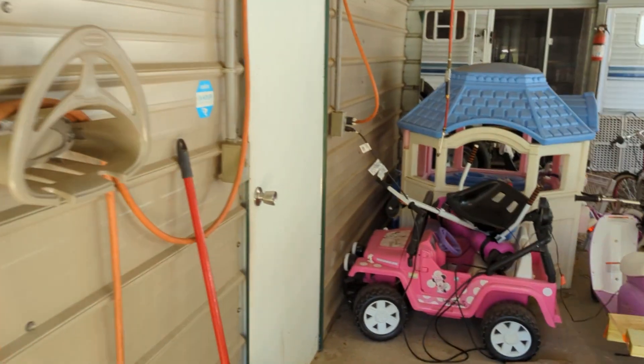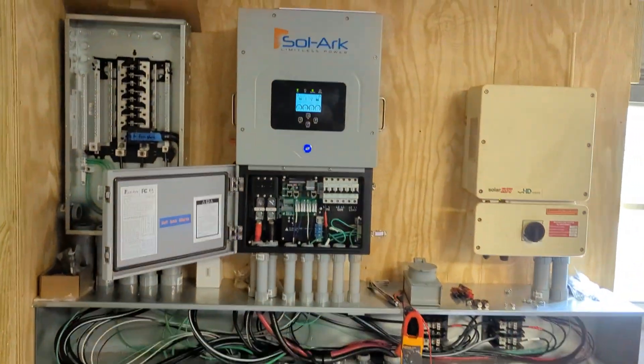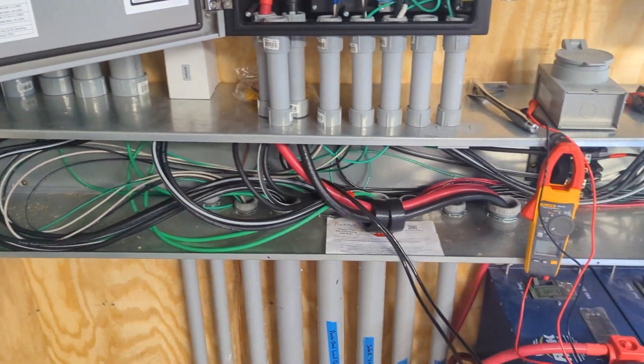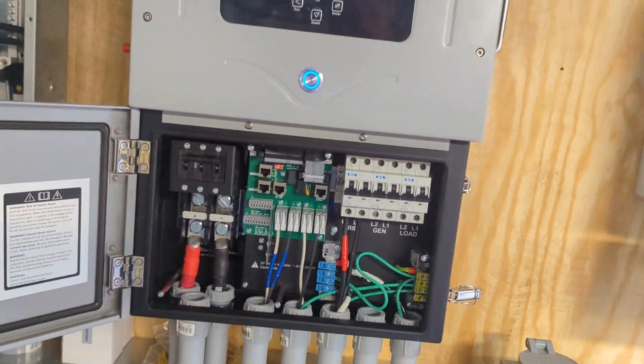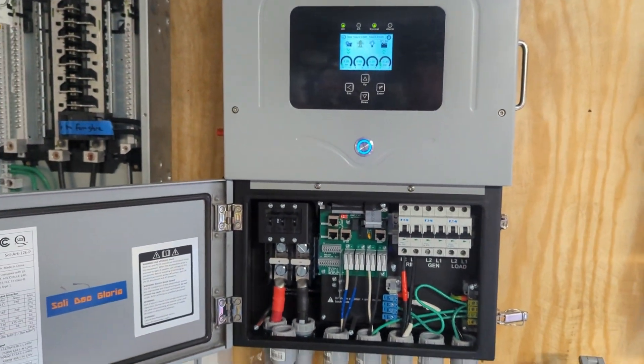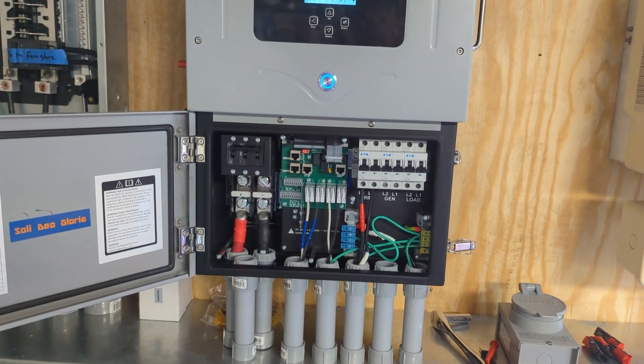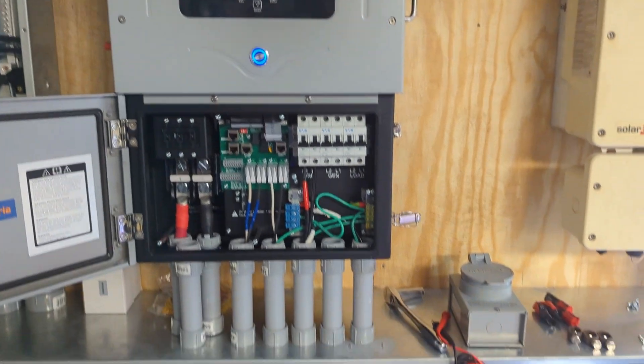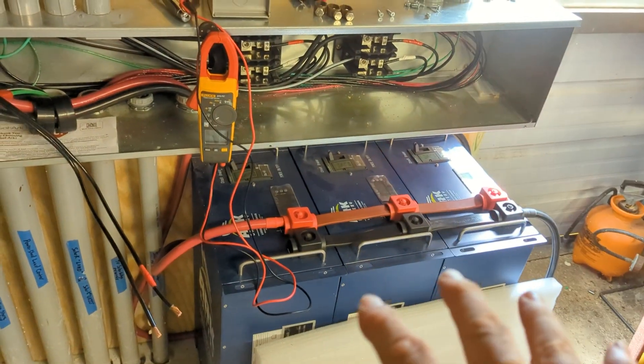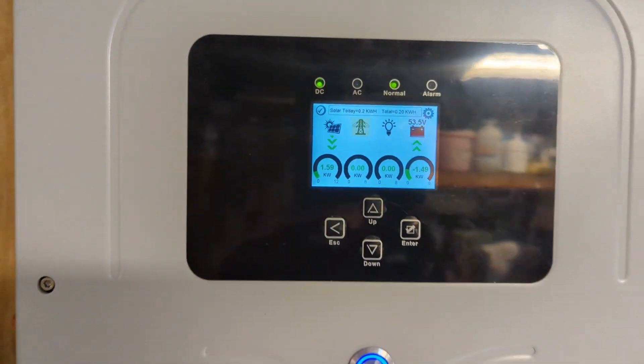We are wrapping up. We fired this up and it is working great. He's just got to finish his wiring. Like the power shed concept — just finalizing a few things. The ground neutral bar — it'll throw a GFDI failure. You need to have everything landed. There's always got to be a neutral and ground bond somewhere in the system, usually at the first main panel, and the solar will detect that you don't have that and throw an alarm — GFDI failure or fault. So we're charging batteries on solar. It's the end of the day, so we don't have that much solar yet, but he's making progress.